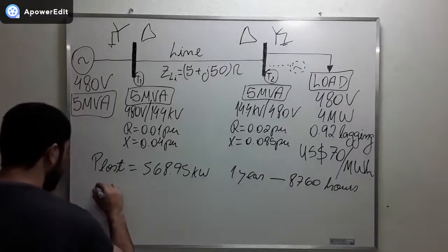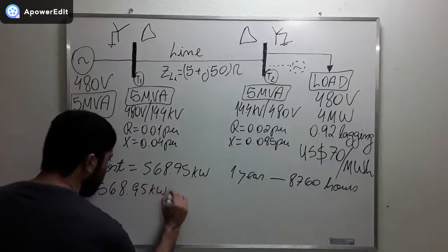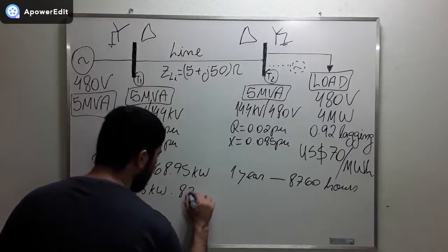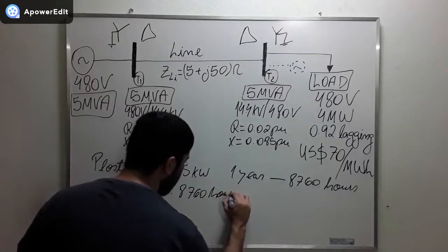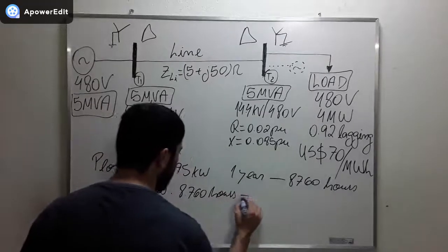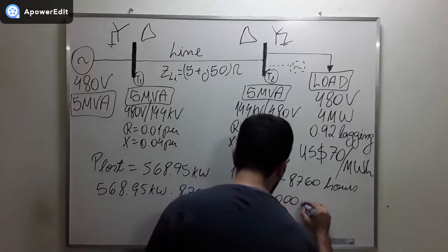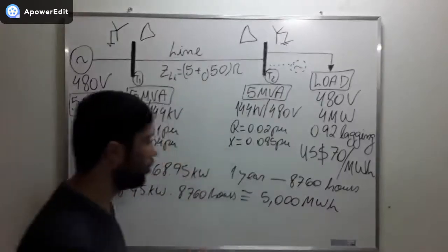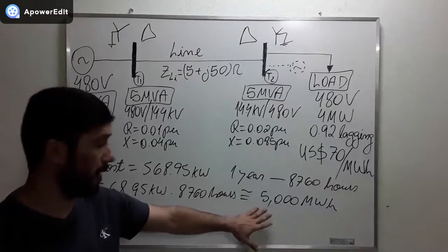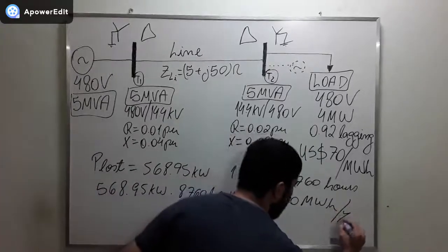Then, if we multiply this 568.95 kilowatts by the amount of hours, 8,760 hours, we get approximately 5,000 megawatt hour. So this is how much we lose. This is the energy, not the power. This is the energy that we lose in a year. So it is per year.